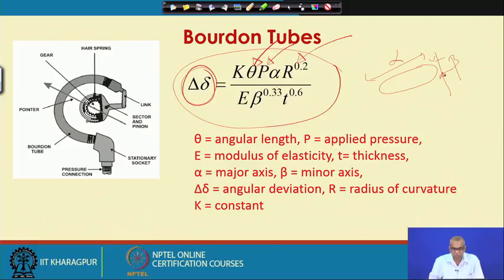Tip displacement is inversely proportional to the modulus of elasticity, and it is also inversely proportional to the thickness of the tube. So, these are the parameters on which the tip deflection of the Bourdon tube will depend. Remember that the tip deflection depends on the modulus of elasticity, and the tip deflection is inversely proportional to the modulus of elasticity.